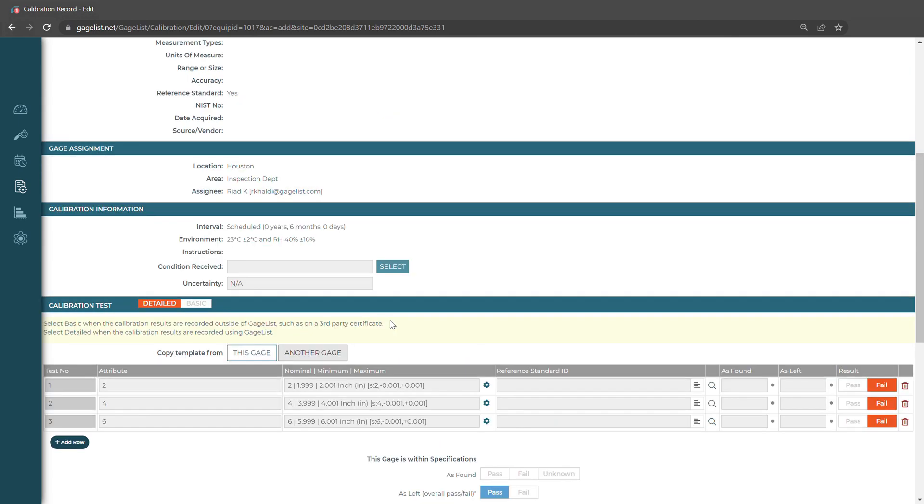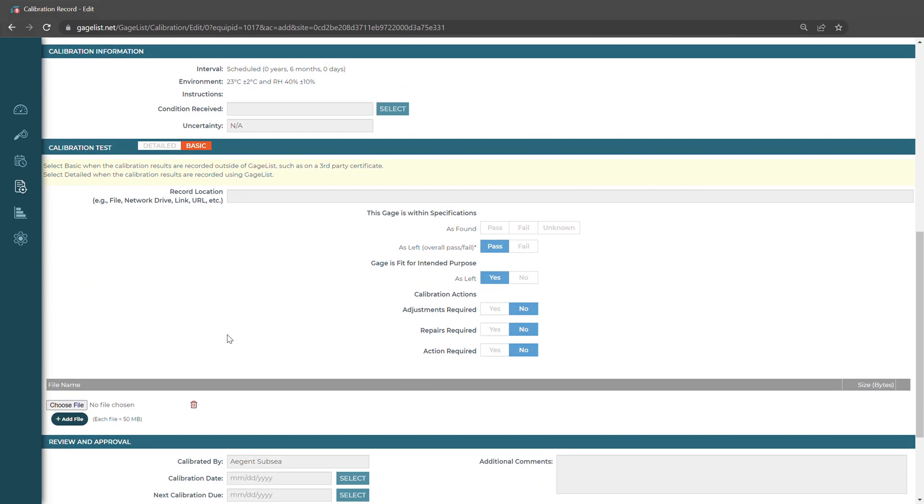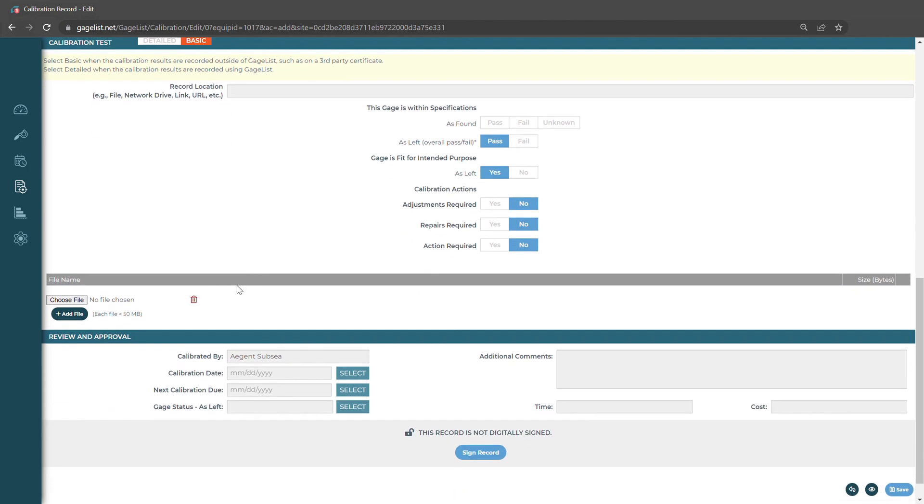If we're just going to be recording an external calibration, we would select Basic. If we want to reference the record location, we can paste the link to it right here. If we have a certificate that we want to upload, we would go here and choose the file that we'd like to upload.